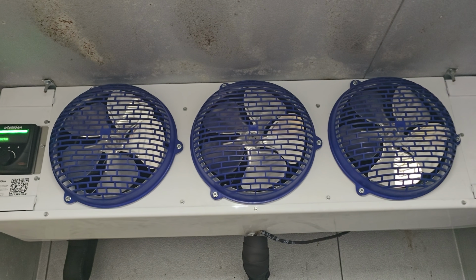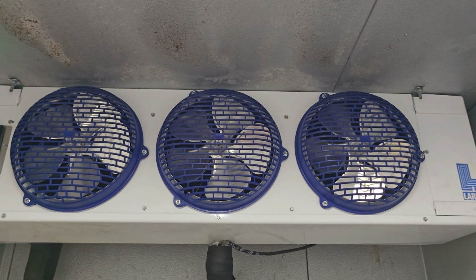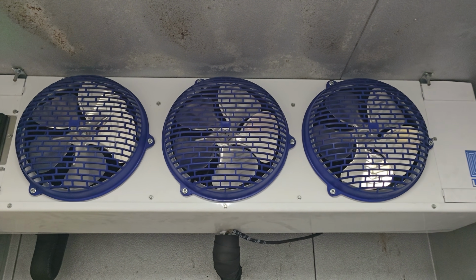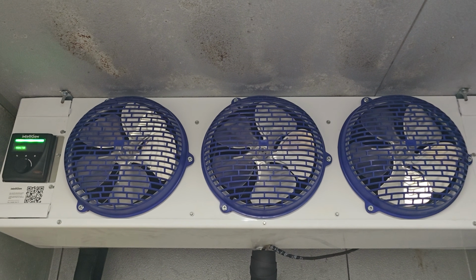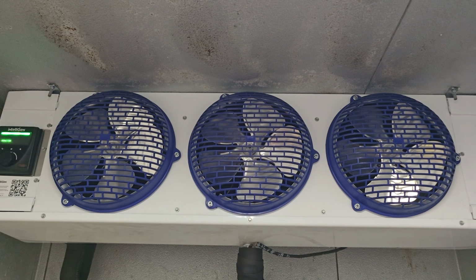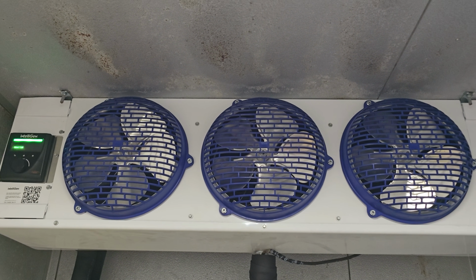Everything's good. We'll still come back in about a day or so just to follow up, because I set the defrost for 20 minutes. They're only maintaining 27 degrees in this box, so it's kind of a hybrid freezer. So we want to make sure that's not too long of a defrost.